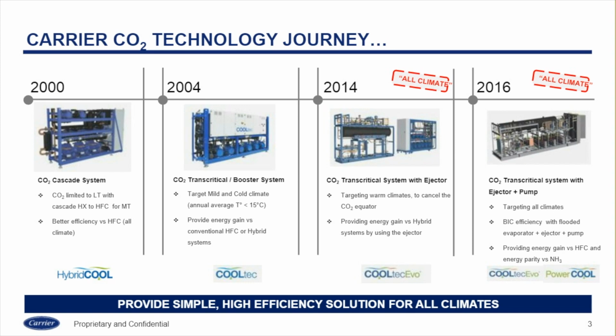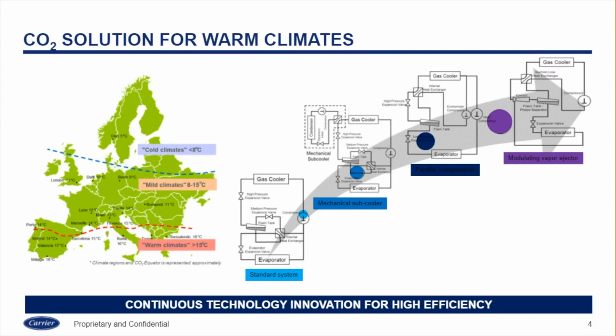Okay, next page, please. This one shows the CO2 solutions for the warm climate. Actually, we aim to introduce CO2 for all climates, and the warm climate has always been the barrier to the technology because of the high pressure of the CO2 at high ambient temperature. So we have different scenarios or technologies to address this high ambient temperature leading to high system pressure, including mechanical subcooling, parallel compression, or the modulating vapor ejector, which is patented by Carrier, to improve the system performance. This is the CO2 solution for warm climate.